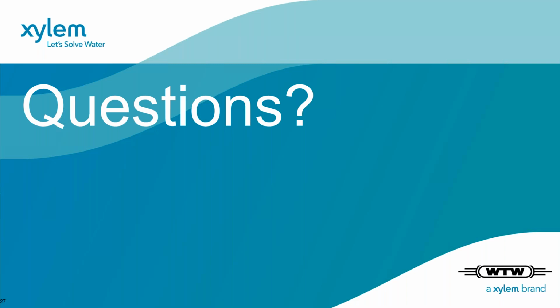Okay, thank you. Is the Alyza only used for ammonia measurement? So it's for one parameter, yes. We have this model for ammonium/ammonia, and we have another model for orthophosphate, but only one parameter each. In addition, if you want to add other parameters like pH, conductivity, or others, you could easily add sensors to the IQ SensorNet as an option, as this is an additional part for the IQ SensorNet.